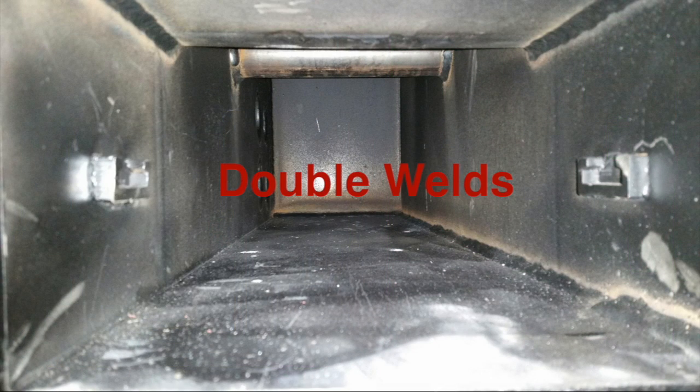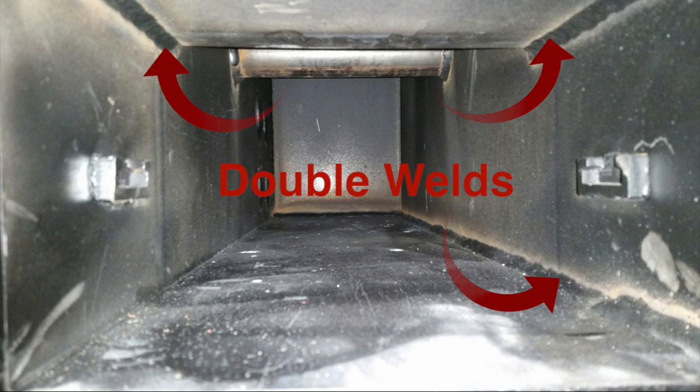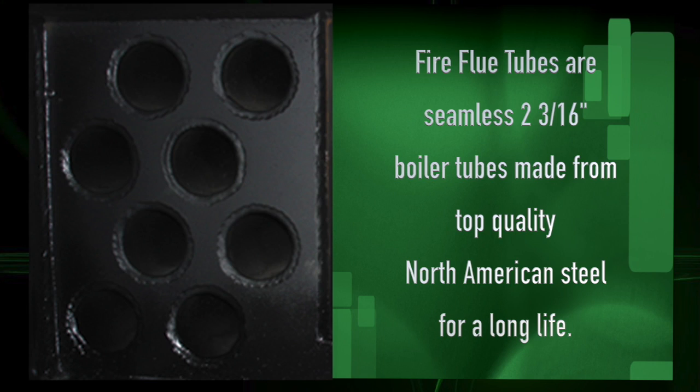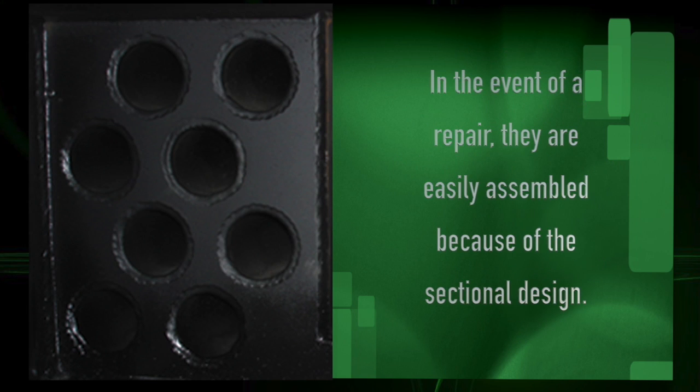We double weld all areas possible to add strength and to help eliminate pinhole leaks. Fire tubes are seamless 2 and 3/16th boiler tubes made from top quality North American steel for a long life. In the event of repair they are easily assembled because of the sectional design.